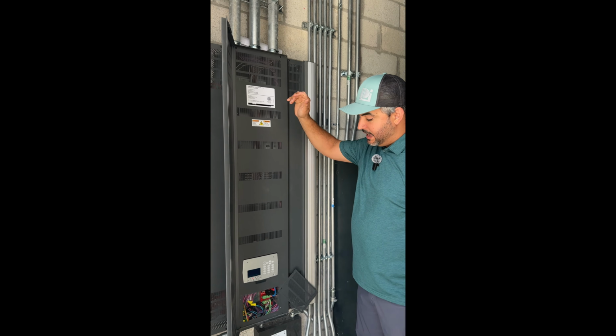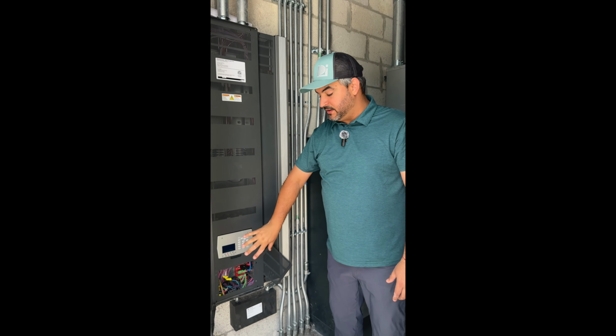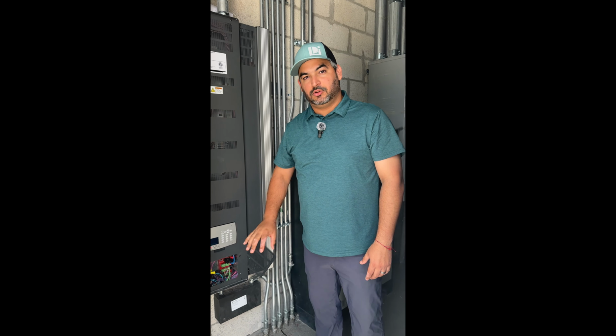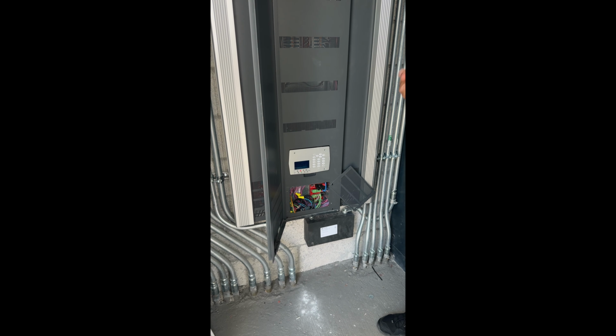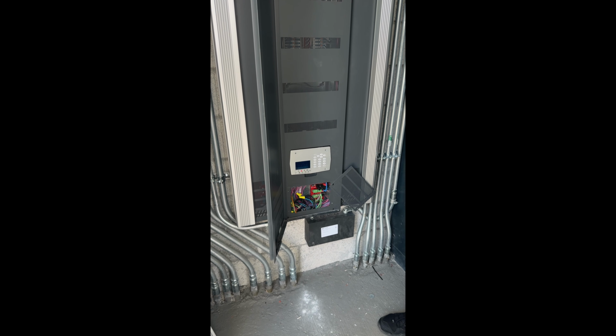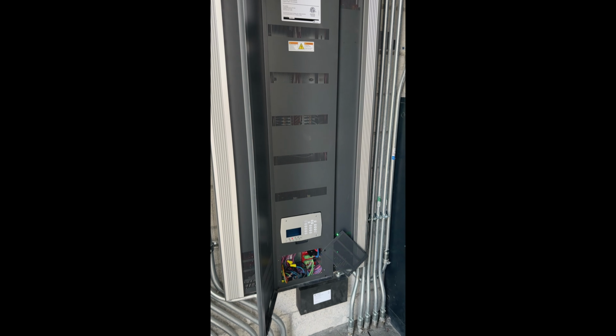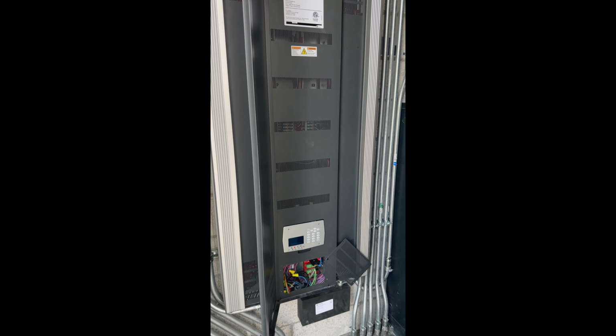10 relays. And we have a time event that is controlling the lights, turning it on 10 minutes before sunset and turning it off 10 minutes after sunrise. In addition to it, it has a photo cell to override in case there is a cloudy scenario during the day. The photo cell wiring is connected down here.